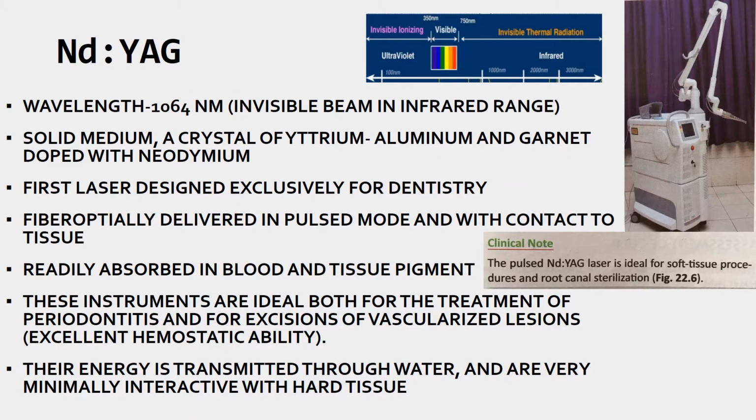Starting with the first one, that is Nd:YAG. So the wavelength for this Nd:YAG is 1064 nanometers. That is, it lies in the infrared range, in this infrared invisible thermal radiation. The active medium is a solid active medium, a crystal of yttrium, aluminium and garnet, which is doped with neodymium. So it was the first laser which was designed exclusively for dentistry.